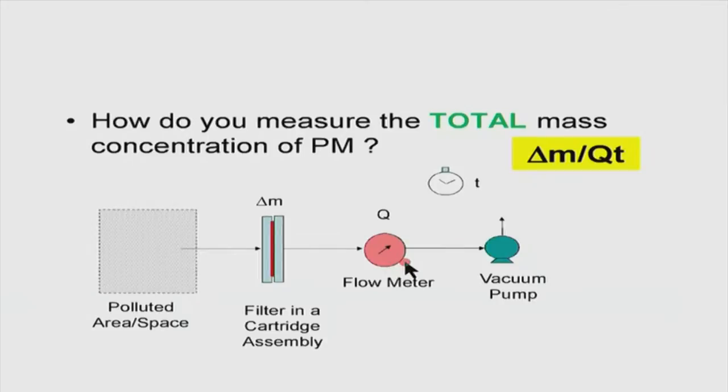One of the things I really emphasize a lot is whether the flow meter is calibrated. Most of the time, the flow meters that are available have a certain calibration, but I just feel much more comfortable if I have calibrated it myself. It is a routine practice in our lab that before any student starts any studies of any kind, the instruments have to be calibrated, and there needs to be a degree of confidence that if I'm saying 10 liters per minute, I actually mean 10 liters per minute, no more, no less.